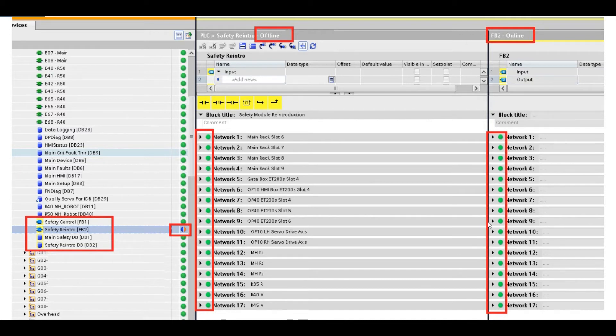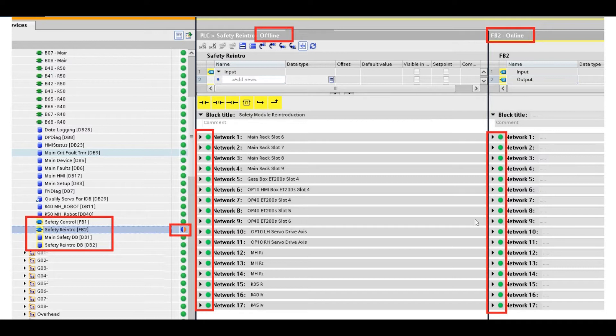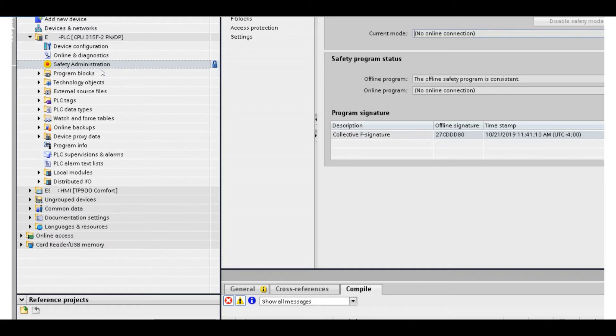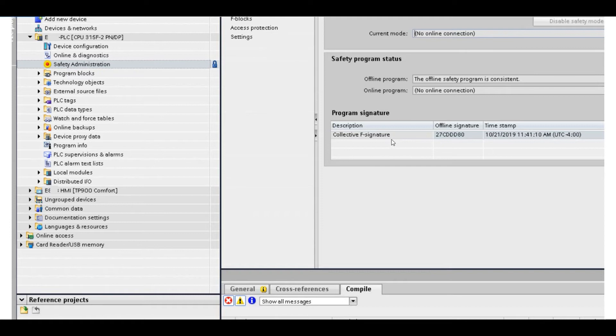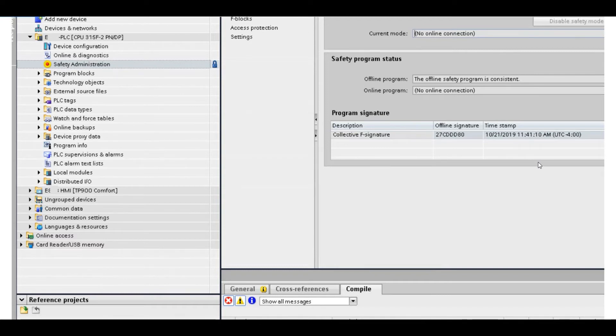Also, if you have some background of Siemens safety, you may think maybe after we compared the signature or the timestamp changed. However, if you go to the safety administration without login, you can still look at the general information, the program signature. You can find this offline signature and timestamp, they all without any change.